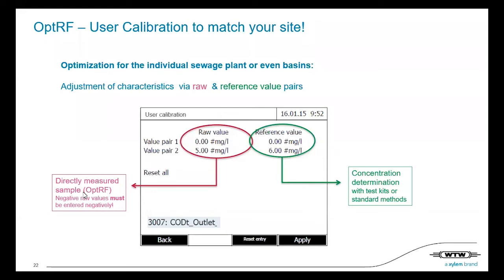And this is the directly measured sample, if you haven't done anything, based on the curve when you start with optical reagent free. And by the way, an important piece of information: it can be a negative raw value, because we do an algorithmic evaluation over a wide scan range. So it can be negative, and if it's negative, you must enter it as a negative value.